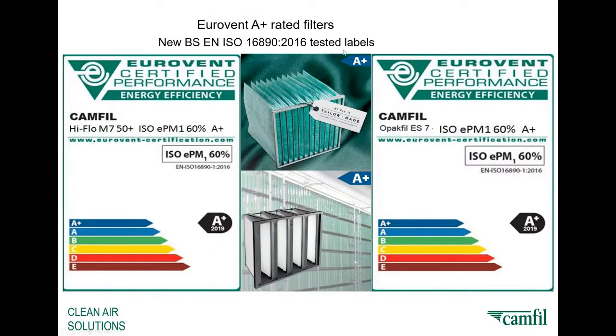Here you can see energy efficiency ratings for filters. These are now published widely on the Eurovent website. An A+ rating for a filter means it's extremely energy efficient, so you get a good combination of filtration efficiency for removing the particles, but also minimum energy consumption based on low operating pressure drop. This particular filter has a 60% PM1 efficiency, whereas some of the low efficiency panel filters on the market have the same energy consumption, but they're only 3% efficient for removing fine particles. This filter can be used as a single stage filter, so it's extremely good.